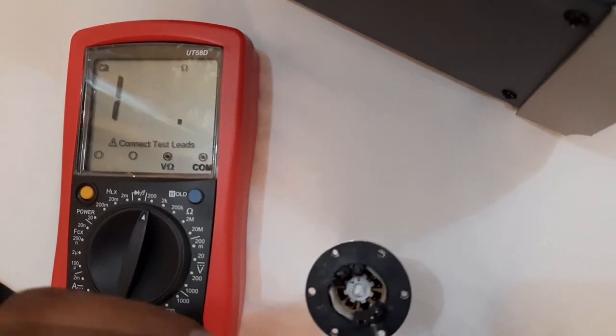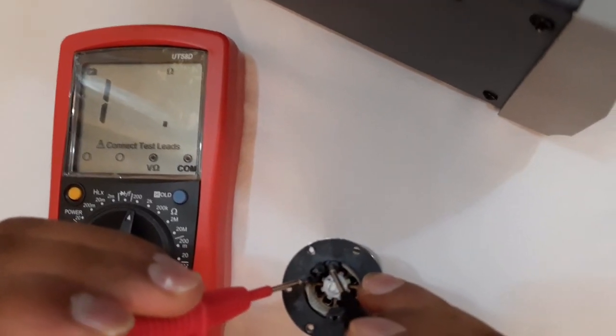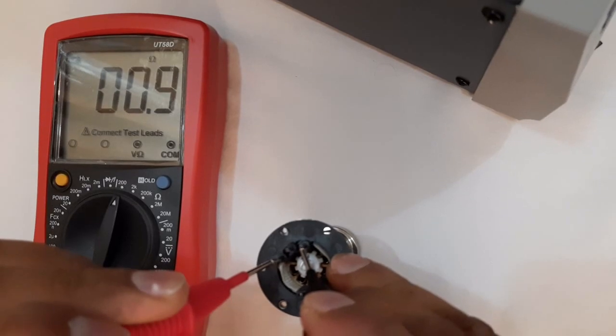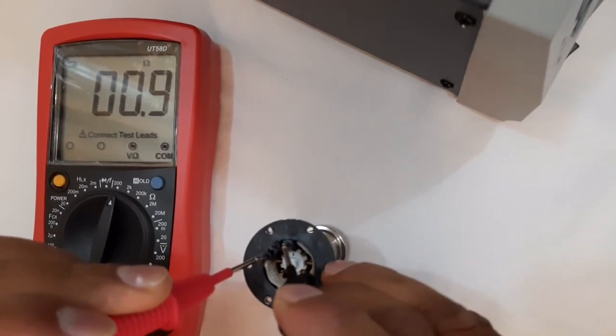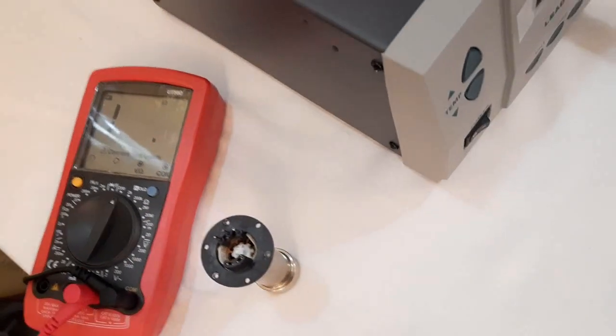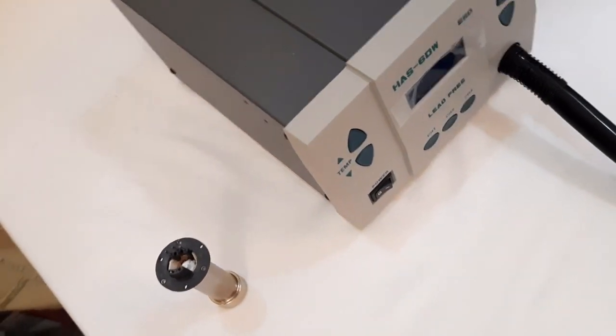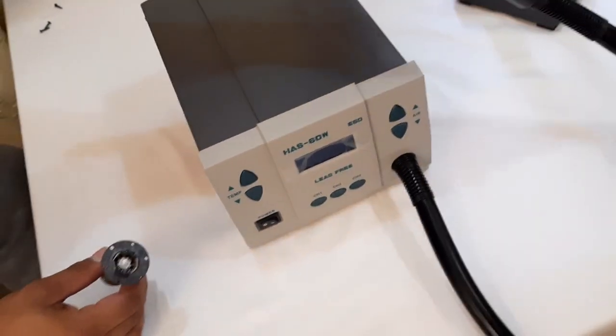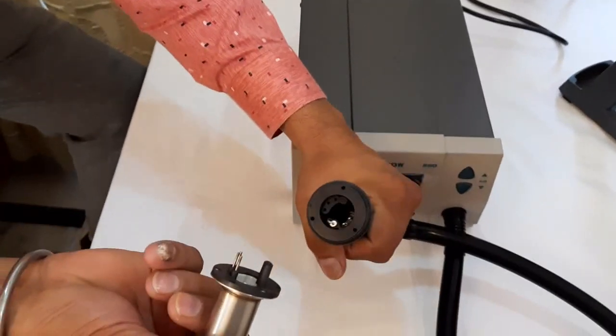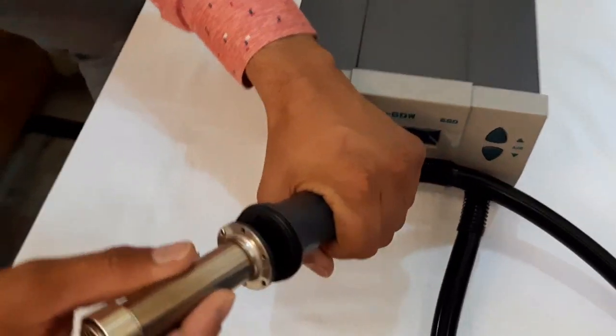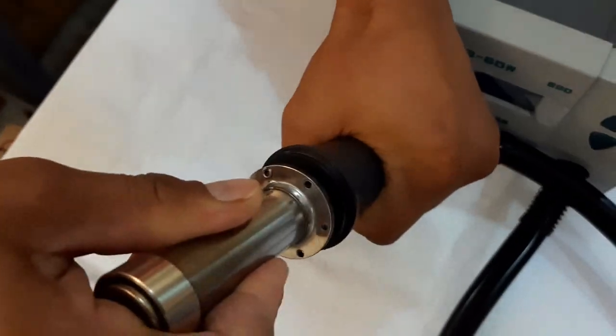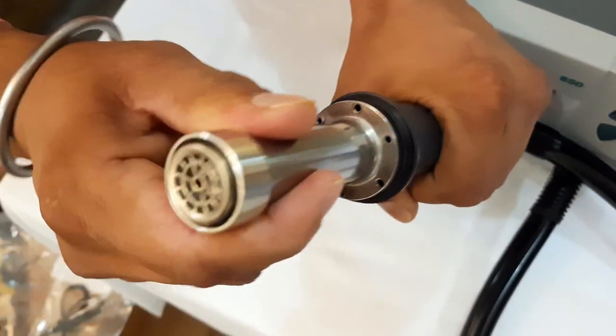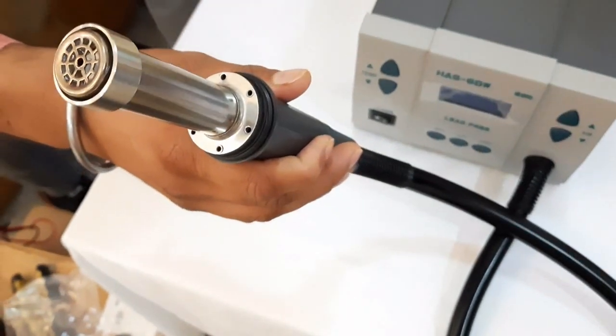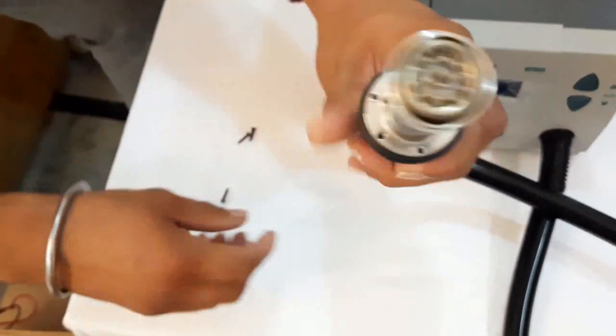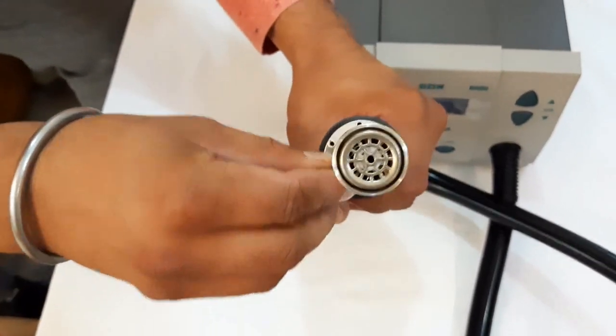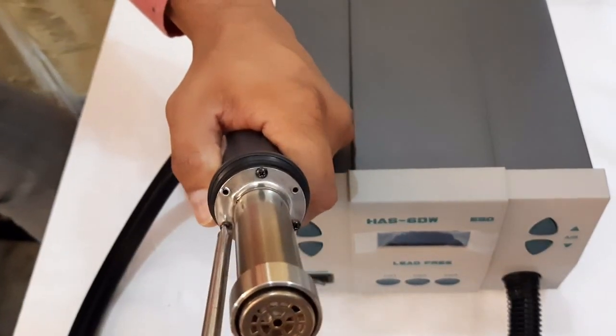Now again we will verify the resistance between these two pins. These two pins denote heating element. So it means the resistance of heating element is also okay. So in this enclosure both the sensor and heating element are okay, and now we will just fix it to the handle, and then we will fix the three screws as well, which we removed earlier. We can see that heating element can be fixed to the handle by pushing it inwards. Now we will fix these 3 screws. Now we have fixed all 3 screws to the handle.